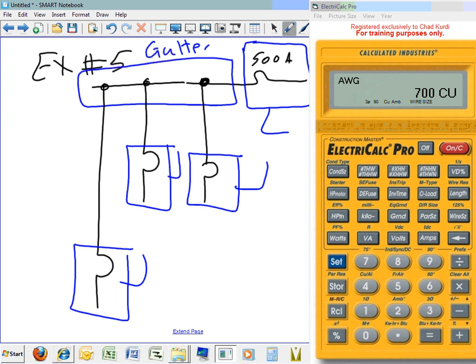Then engineers grab these circuit breakers and put them in a panel. A panel is more reliable than a gutter. That's what it is. And there's a limitation on how far you can go from here to here. We'll talk about the limitations. There are 2 limitations. There's the 10-foot rule, guys. I'm going to do this one as from here to here, 10 feet. And from here to here, 10 feet. And from here to here, 25 feet. So I'm going to do two of them, 10 and 10.